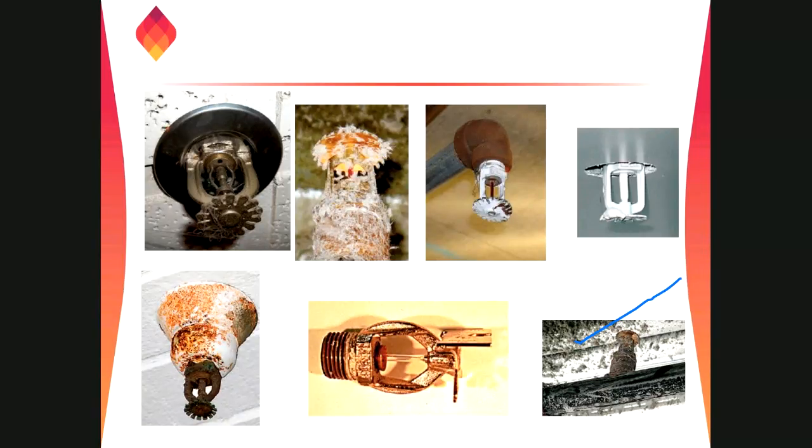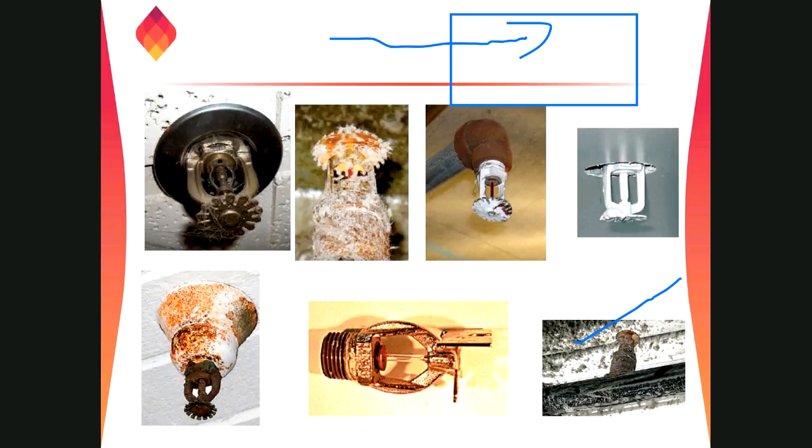Who is responsible for checking the sprinklers? If this is your building, you install your sprinkler system, and before that a person will come from civil defense to approve the plan. If he comes to this side and sees it looking like this one, he will say no, it is not possible. Try to replace all the heads.